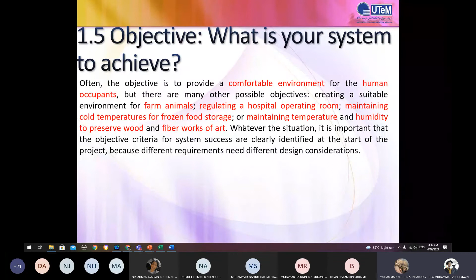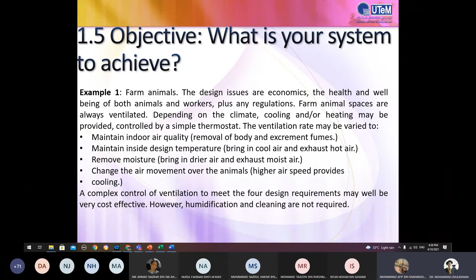Then this is an example of application in HVAC. Okay, we take the first example, farm animals. The design issues are economics and the health and well-being of both animal and worker, plus any regulation. Farm animal spaces are always ventilated depending on the climate. Cooling and/or heating may be provided, controlled by a simple thermostat. The ventilation rate may be varied to maintain indoor air quality, remove body and excrement fumes, maintain the inside design temperature, remove moisture, and change the air movement over the animal. This is a suggestion of what we need to control inside the design.